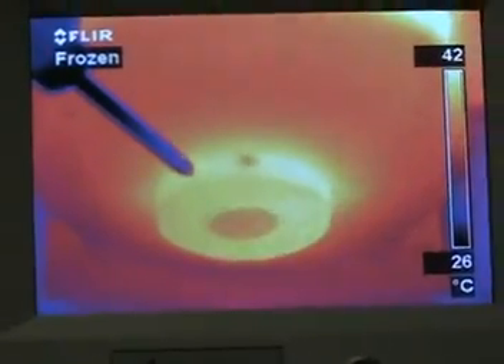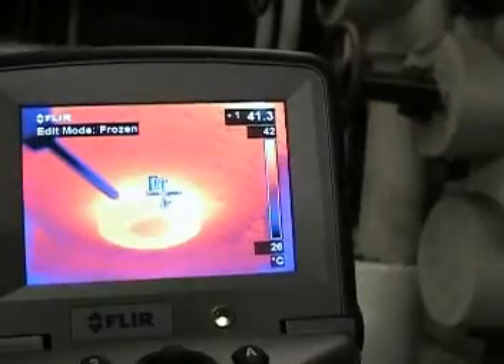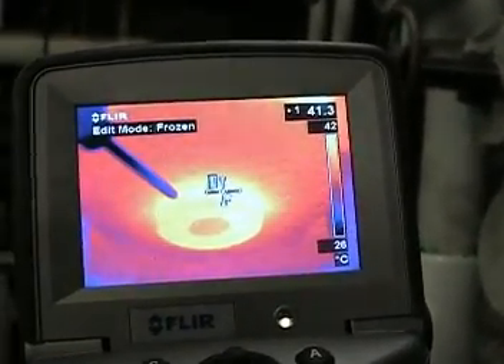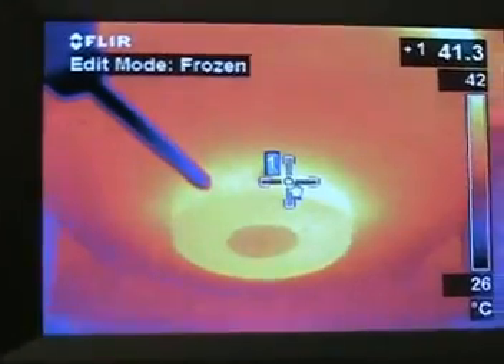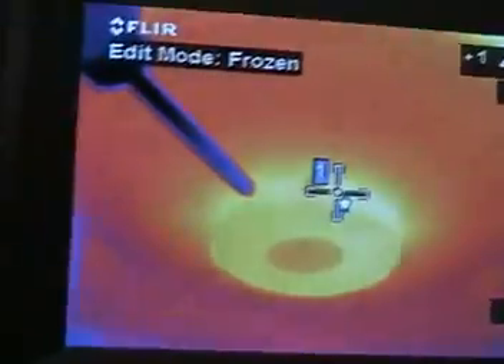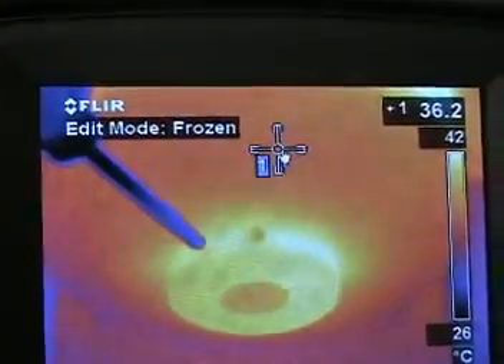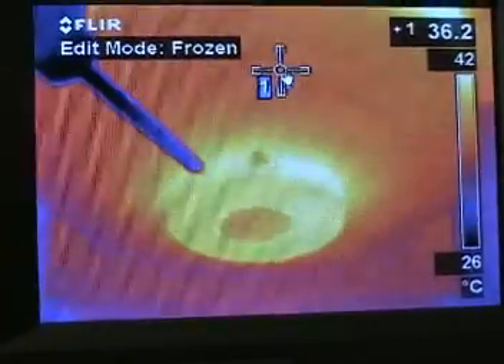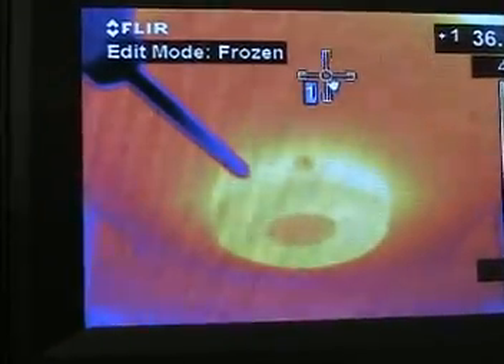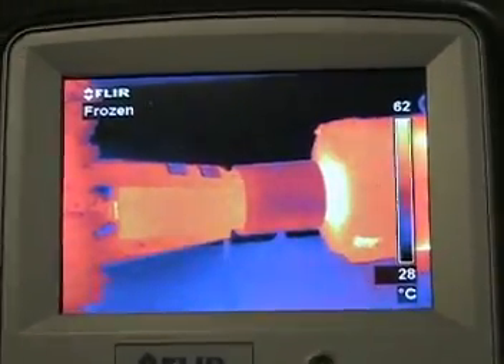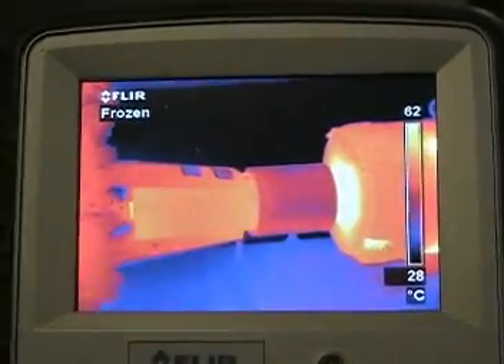We now take a temperature reading of the back bearing. It's only a 5 degrees centigrade difference between it and the motor housing. It is, however, 15 degrees centigrade cooler than the front bearing. As we compare the temperature of the pump to the front bearing, we see the pump is relatively cool. This is not a source of heat transfer through the shaft to the motor.